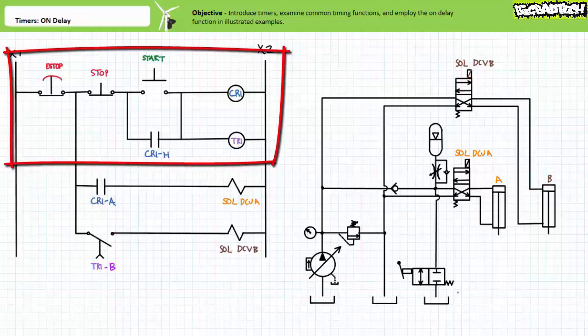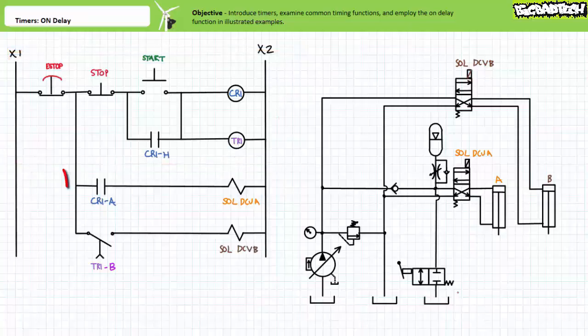The 3-wire control circuit in rungs 1 and 2 serves to energize the coil of a regular control relay CR1 and the coil of a timer relay TR1. Contact CR1H associated with a regular control relay serves as a holding contact, allowing the circuit to maintain the last asserted state. Note the inclusion of a maintained E-stop that serves to de-energize the whole system.